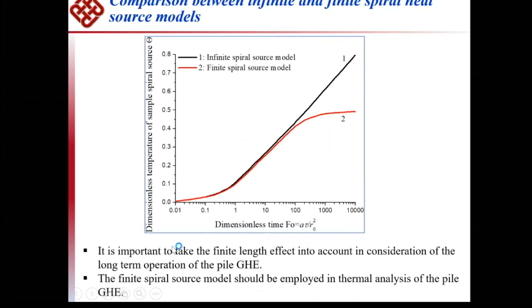Our conclusion is that we have to take the finite length effect into account in consideration of the long-term operation of the ground heat exchanger. The finite spiral source model should be employed in thermal analysis of the pile ground source heat pump, ground heat exchanger. So don't use an infinite spiral source model for long-time simulation.